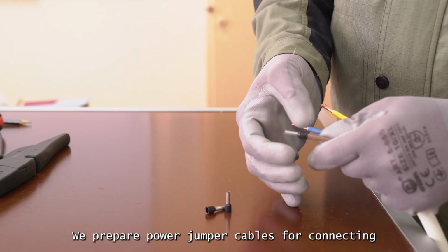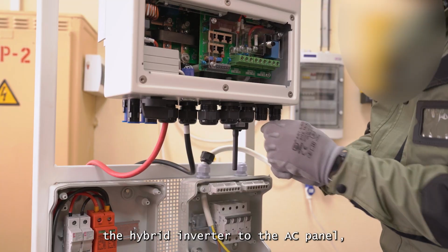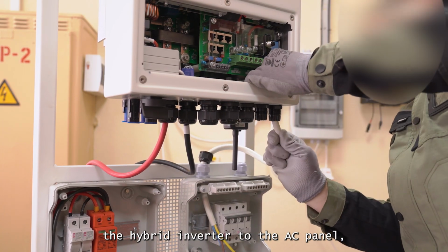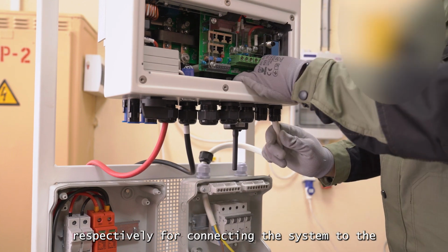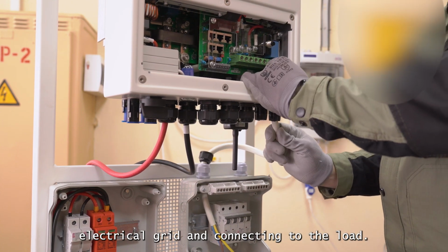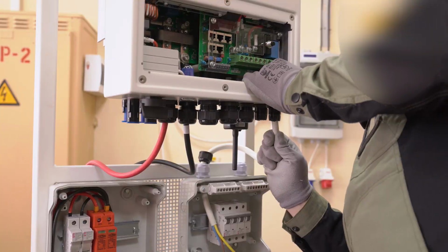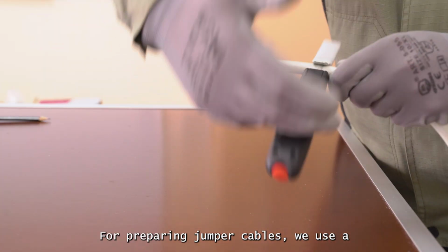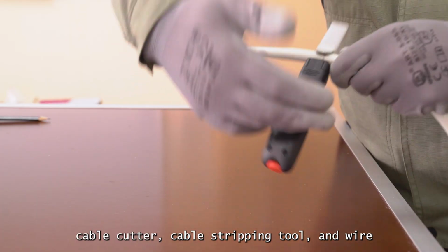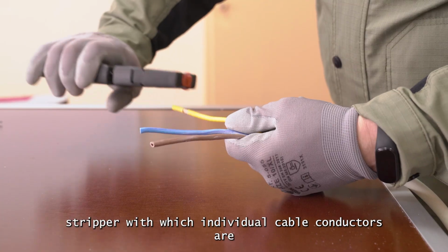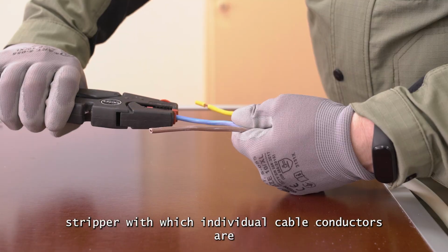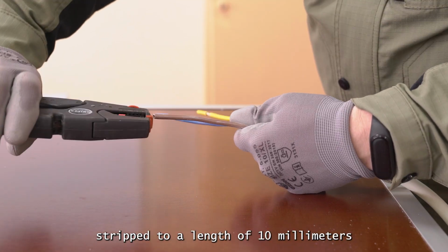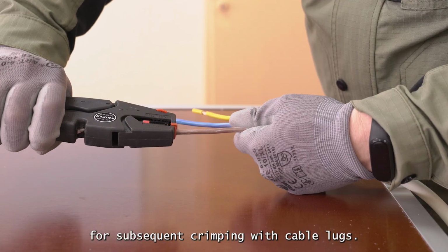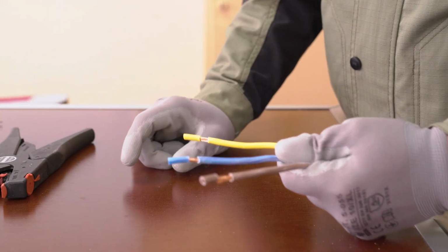We prepare power jumper cables for connecting the hybrid inverter to the AC panel, respectively for connecting the system to the electrical grid and connecting to the load. For preparing jumper cables, we use a cable cutter, cable stripping tool, and wire stripper with which individual cable conductors are stripped to a length of 10 millimeters for subsequent crimping with cable lugs.